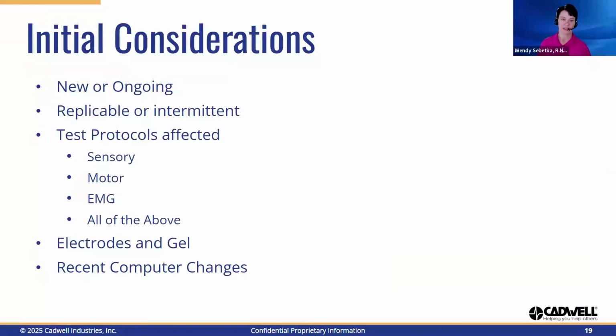Some important details to make note of regarding the noise relate to the timeline, consistency, and test protocols affected. These details will tell you a great deal of information about the noise and how to troubleshoot it. Ongoing intermittent issues that occur in all test protocols are typically more difficult to resolve as compared to new replicable localized issues. It is a common misconception that reusable electrodes and wires last forever and don't need to be replaced.